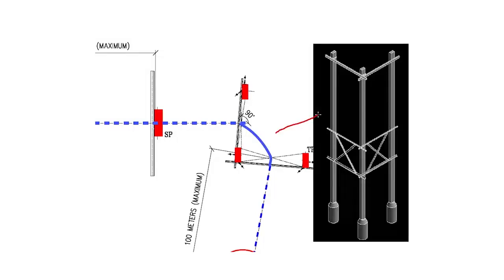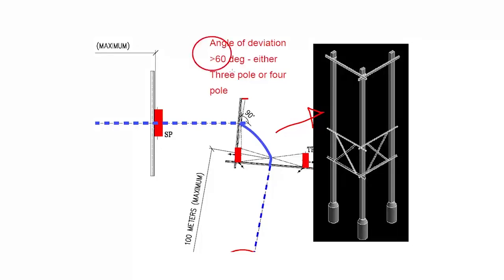Generally for 90 degrees, 3 poles are to be used, and the cut point needs to be taken in such a fashion as shown in the isometric view. 3 poles through which the line goes and takes the turn to the left at 90 degrees. The isometric view indicates how the structures are being used to brace all the 3 poles. So when the angle of deviation is greater than 60 degrees, we can use either a 3 pole structure or we can use a 4 pole and corresponding structures.